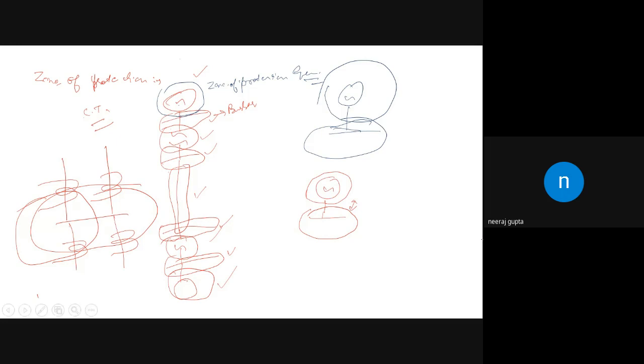So it is the CT which decides where the zone is created, because we are getting the information from this CT. From the current transformer we are getting the information, and if we want the information from the zones that are overlapping, we have to place the CT here. Suppose we place one CT here and another CT somewhere here, in that case it will get the information from here only, but that is not good as far as the protection system is concerned. We have to overlap the zones. So instead of taking the CT here, we place this CT here, and as a result the zone of protection is created because of that. So the zones of protection must overlap so that the system will not remain unprotected.